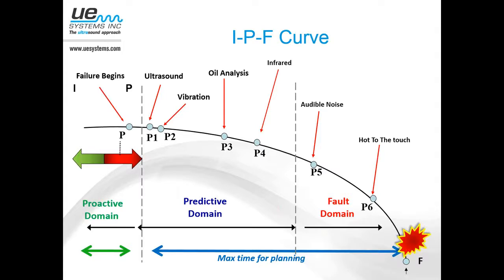In other words, could you go into that proactive domain and think to yourself, well, I've got the ability to go buy a higher quality quick disconnect, or I've got the ability when I install my compressed air system to use hard piping rather than run hundreds of yards of flexible hose, which is more likely to spring a leak. So there are things that you need to think about, and the information that these condition monitoring technologies give you when you find these problems is just the tip of the iceberg. You need to go back and think, okay, we found these failures. Now, what was the original cause of these failures? Was there a way we could prevent them?